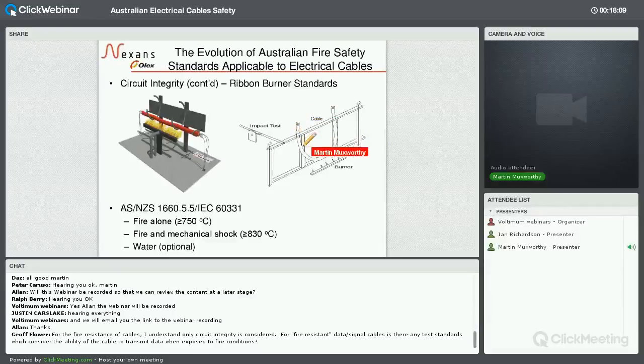And what this little picture here is meant to describe is the cable itself is clamped to a metallic ladder type tray. The burner is positioned to obviously burn the cable, and then an iron bar is repeatedly struck against the tray to introduce a mechanical shock. And it's really, I guess, a more severe or onerous way of proving that a cable is going to survive in its more practical application. Fire and mechanical shock is normally done at 830 degrees, and it's interesting reading through the standards how you actually validate the temperature of these tests.